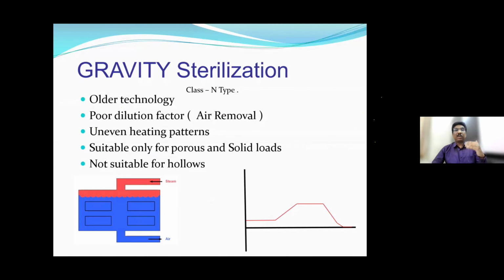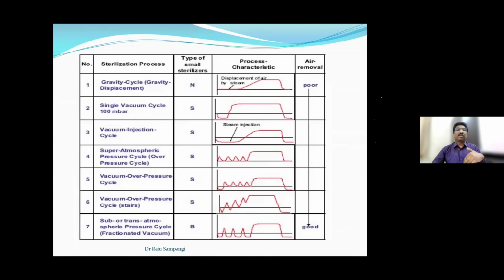The Class N autoclave is older technology, wherein the air removal was poor. And the air removal improves when you go to the Class B. There are various mechanisms which are used to remove the air. And when you are doing a pulsed vacuum or a fractionated vacuum, that's when the air removal is said to be good. So the Class B can be very useful when it comes to ophthalmology, because we use lumened instruments.